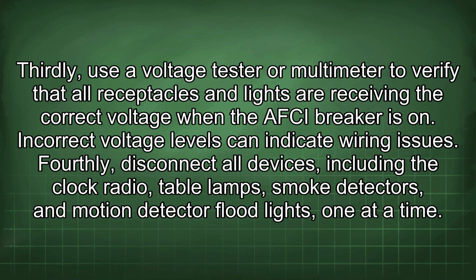Thirdly, use a voltage tester or multimeter to verify that all receptacles and lights are receiving the correct voltage when the AFCI breaker is on. Incorrect voltage levels can indicate wiring issues.